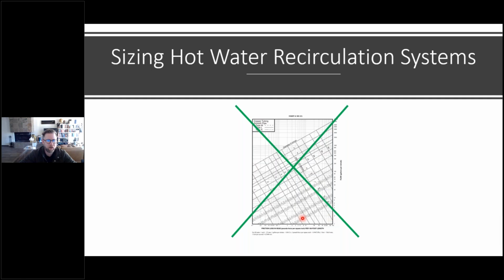So if we base our flow rates only on velocity and flow, you don't have control, because pumps are not sized based off velocity, they're sized off of pressure drop. Your pressure drop and your flow rate have to be adequate for your system to work. So we don't just use velocity. So that's what this first X is.